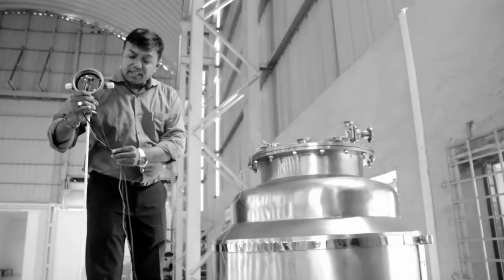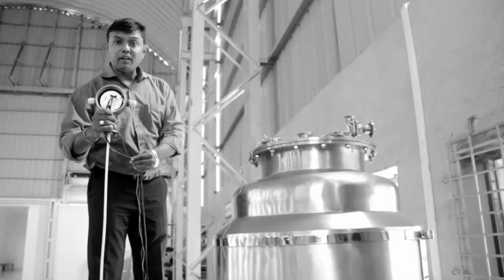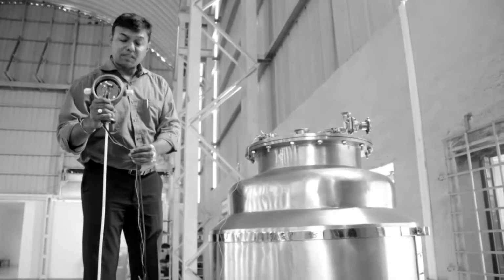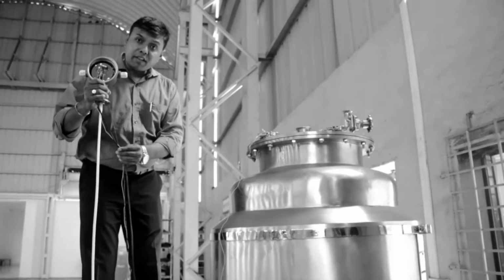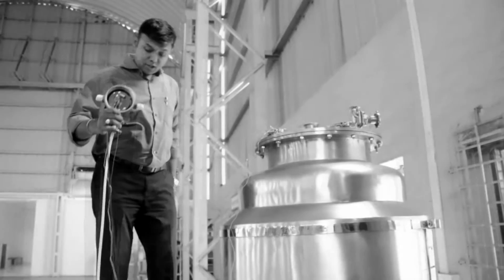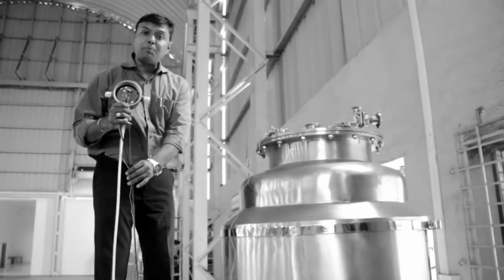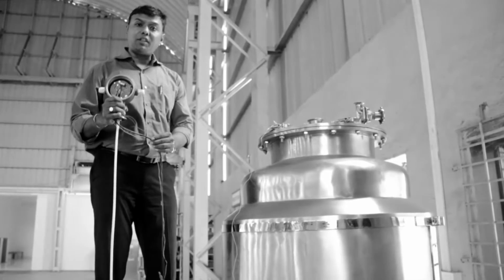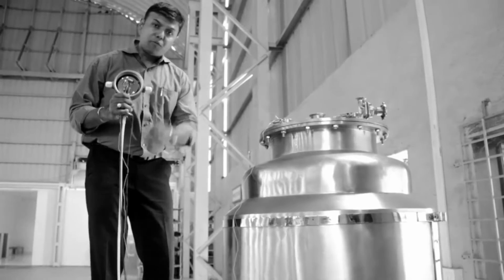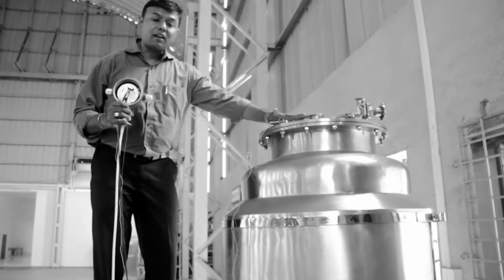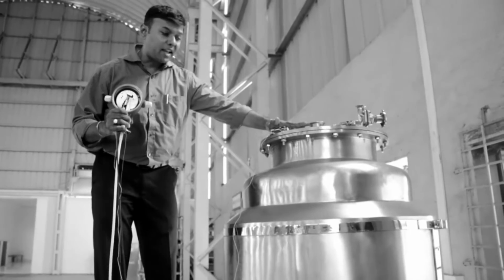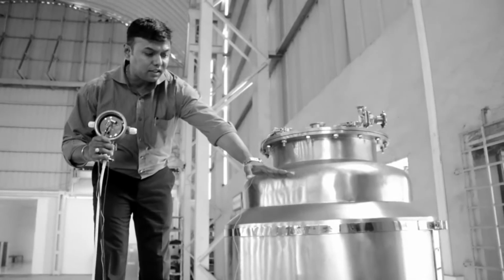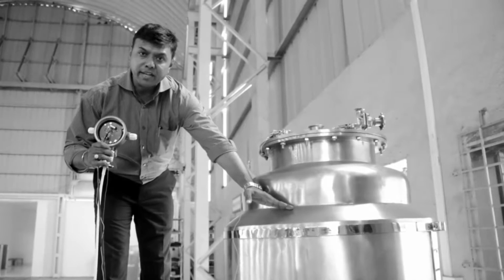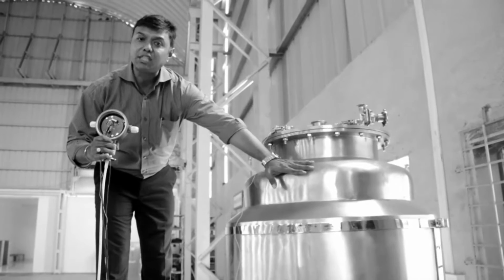You have seen that we have connected the instrument with the 24 volts DC plus and minus, and then we have given the output to the multimeter. So before we start with the calibration process, there are two essential things which we've got to do. First, you got to fill up the tank till where you need the 20 milliamps. So we have filled up this tank till this portion, till where we need the 20 milliamps. So this tank is full.